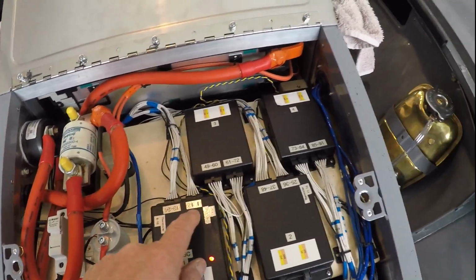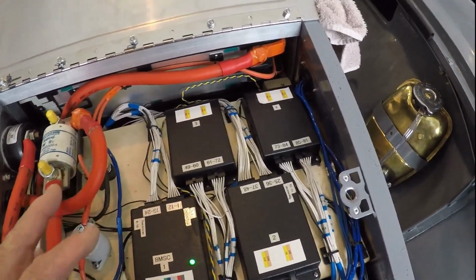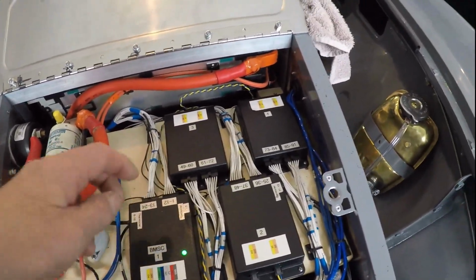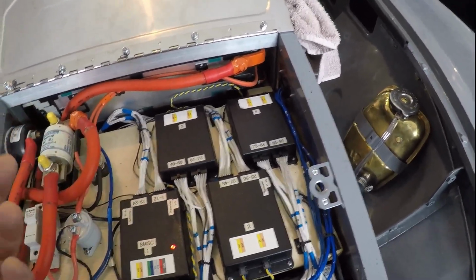Here's 1 to 12. Evidently this plug was not tightly installed, because as soon as I wiggled that and made sure it was in all the way, the fault immediately went away. So that was, fortunately, just a loose connection to the plug.